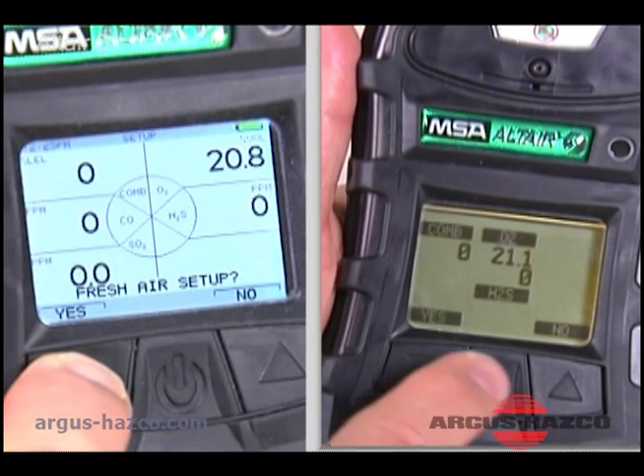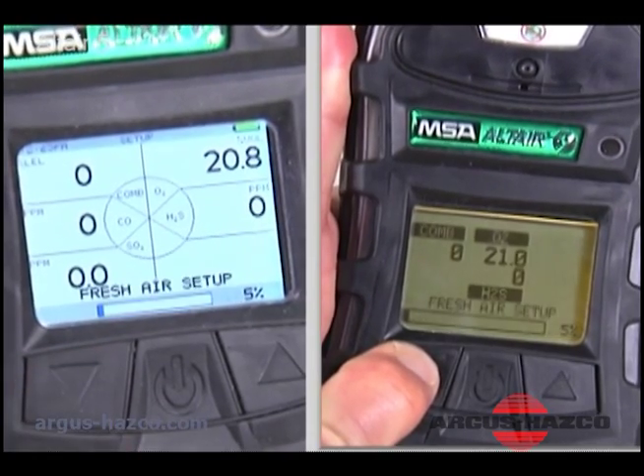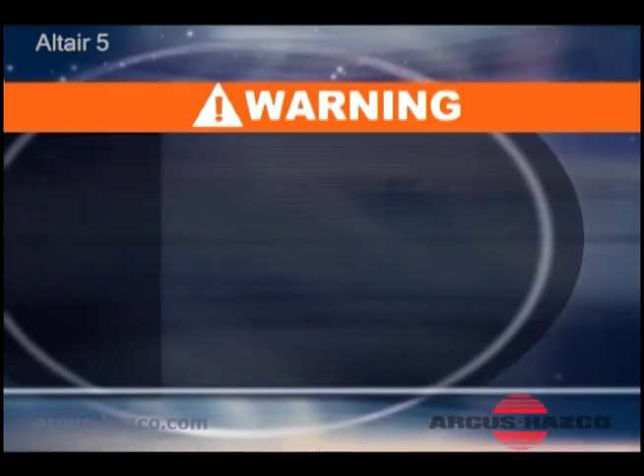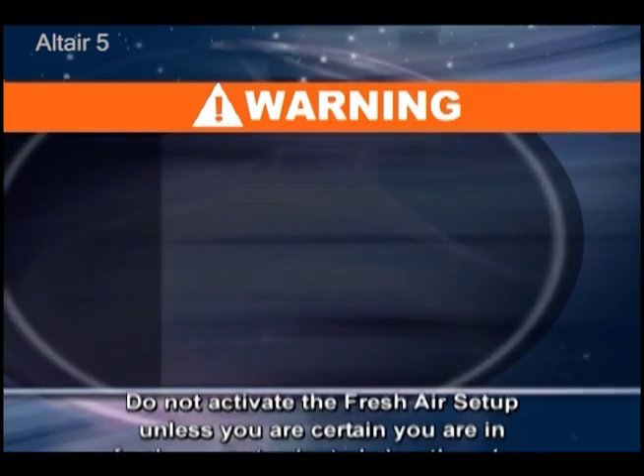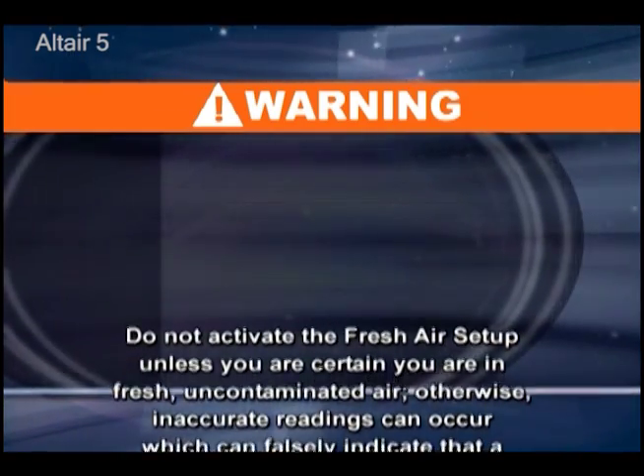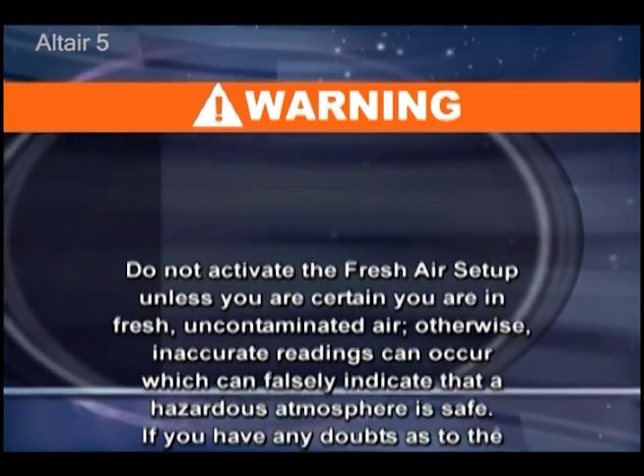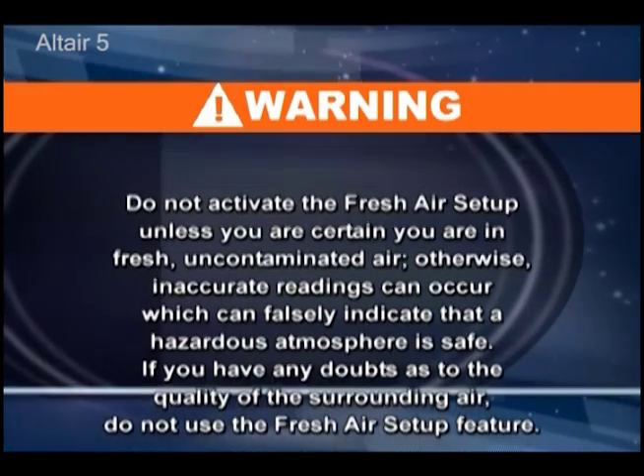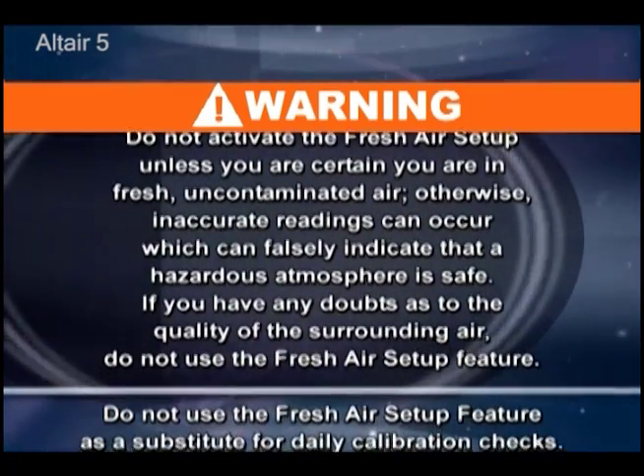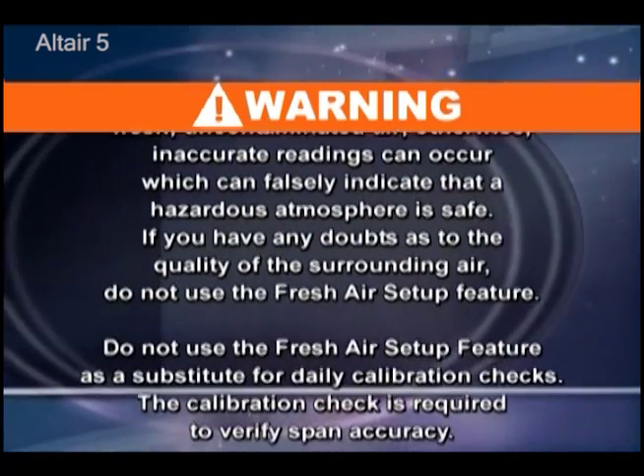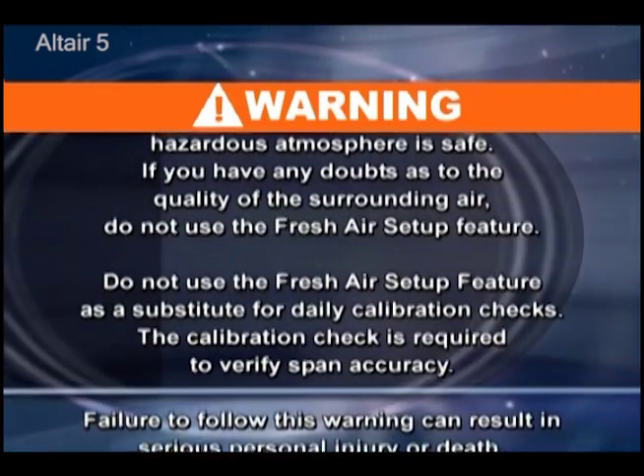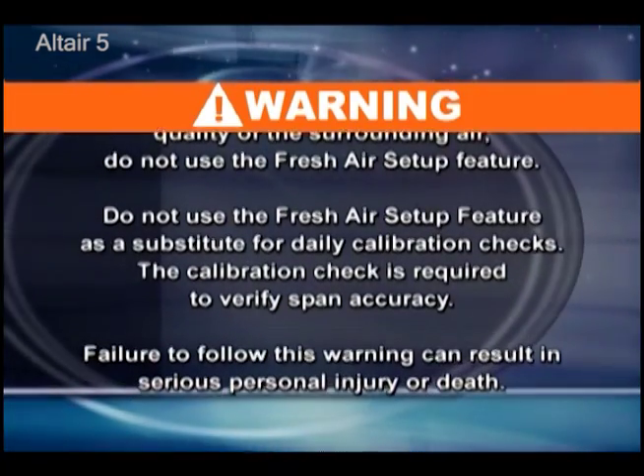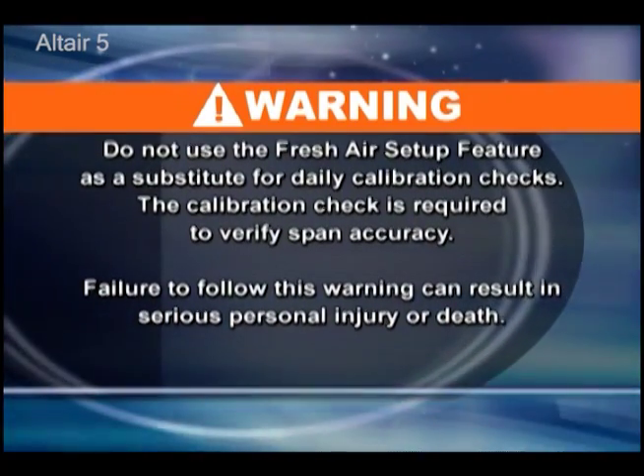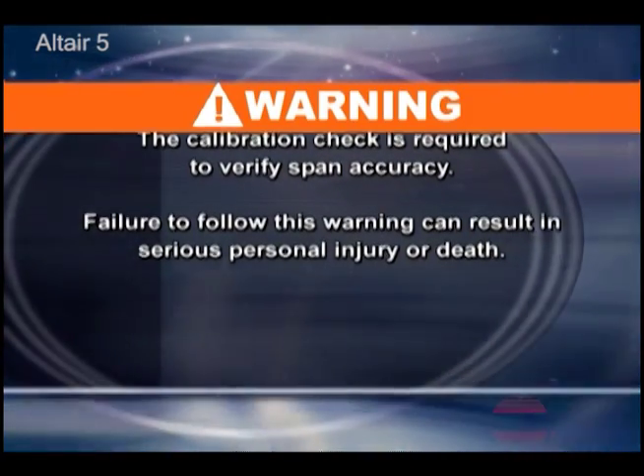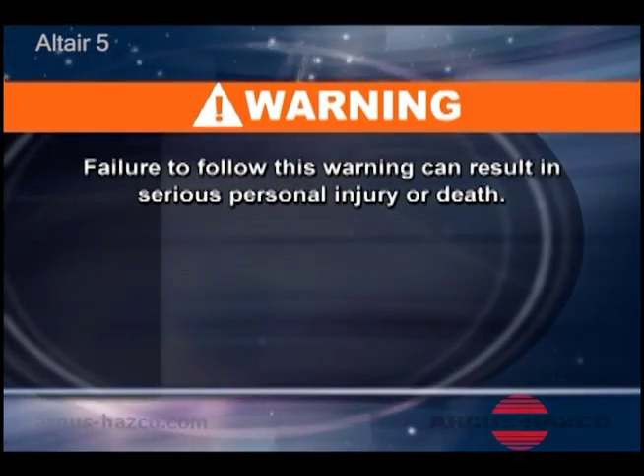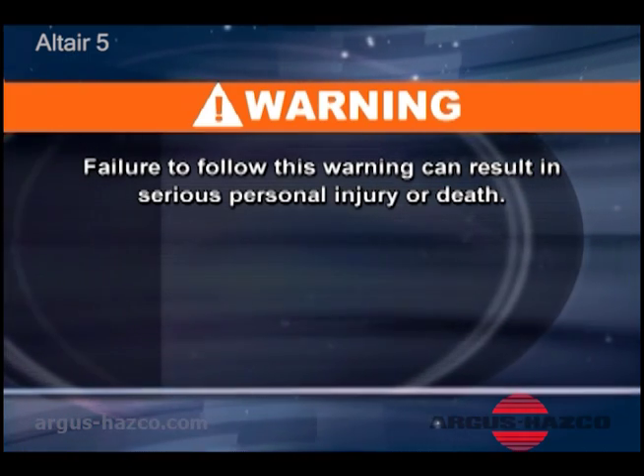If the instrument detects a hazardous gas concentration, it will ignore the fresh air setup command and enter an alarm state. Do not activate the fresh air setup unless you are certain you are in fresh, uncontaminated air. Otherwise, inaccurate readings can occur which can falsely indicate that a hazardous atmosphere is safe. If you have any doubts as to the quality of the surrounding air, do not use the fresh air setup feature. Do not use the fresh air setup as a substitute for daily calibration checks. The calibration check is required to verify span accuracy. Failure to follow this warning can result in serious personal injury or death.